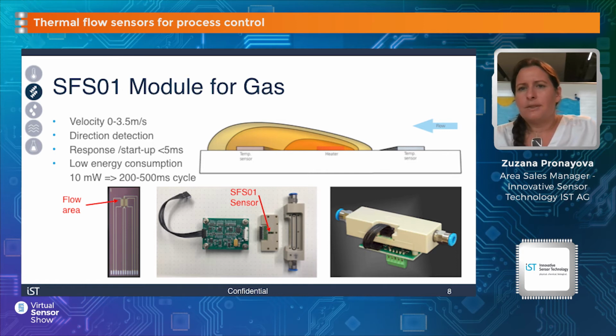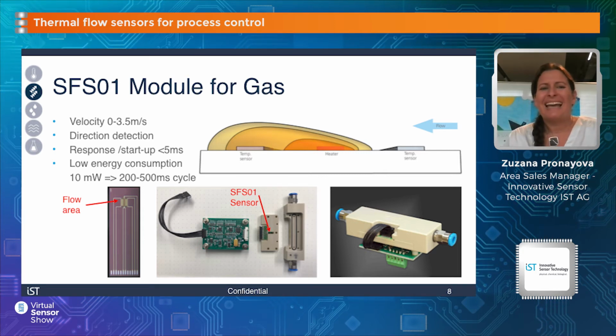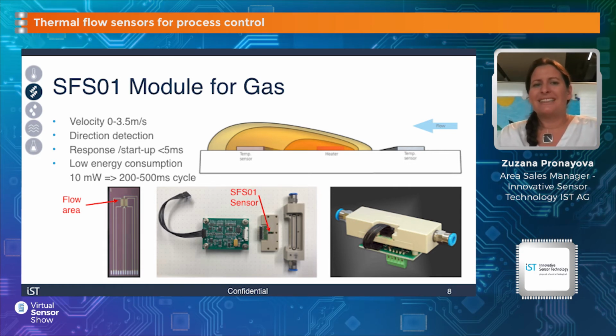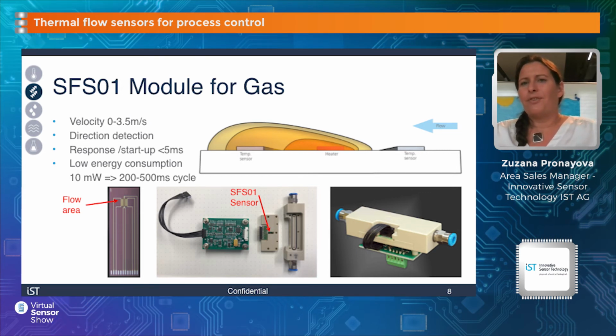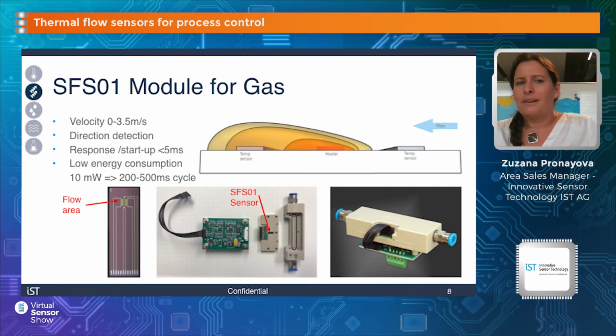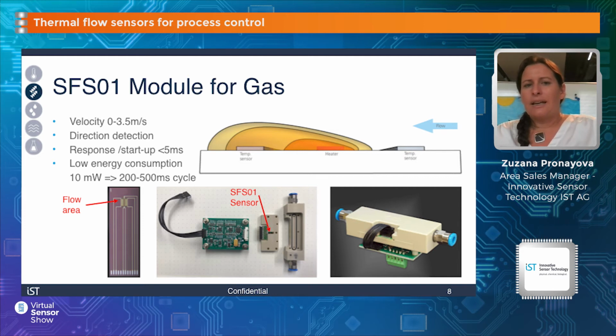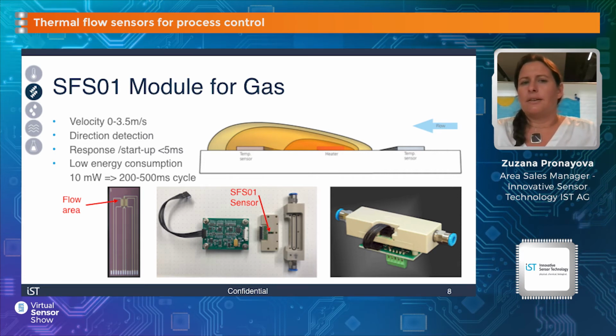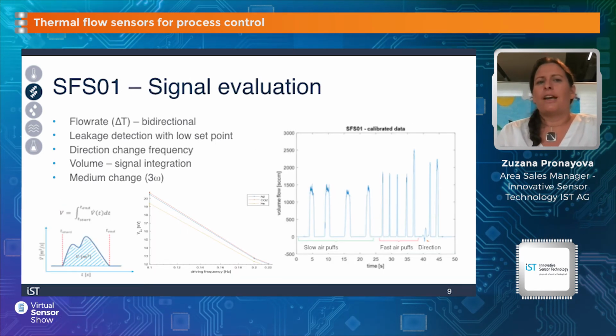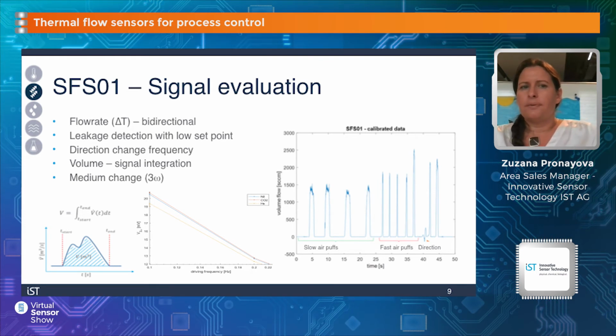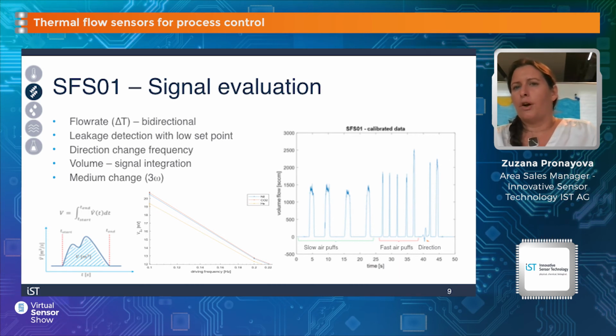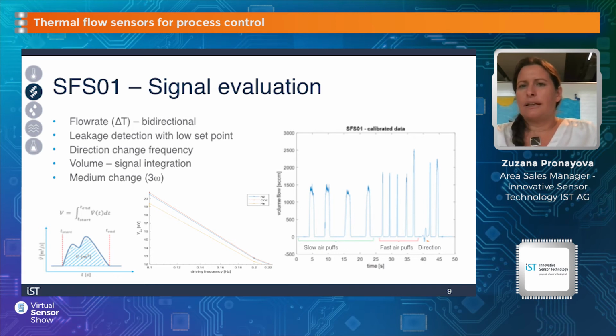What this system allows us as well is to determine the flow direction. At the same time, this calorimetric principle allows us to detect the flow direction. Just as for us, breathing is a sign of life, for a machine, the backflow can be a warning signal indicating a malfunctioning valve or that a seal broke. So how can we evaluate the signal from such a sensitive gas flow sensor? First, we can of course accurately measure very small flow rates. In a well-defined flow channel, this is true in both directions. And a set point in one of these directions can then indicate a leak in the system.